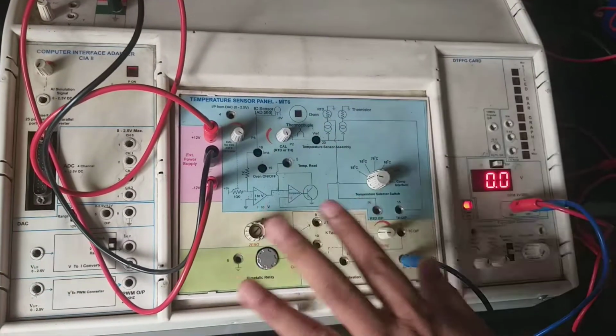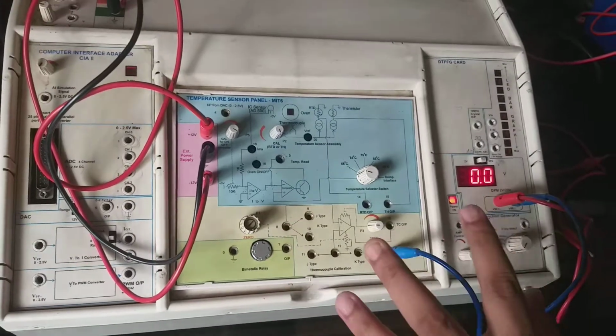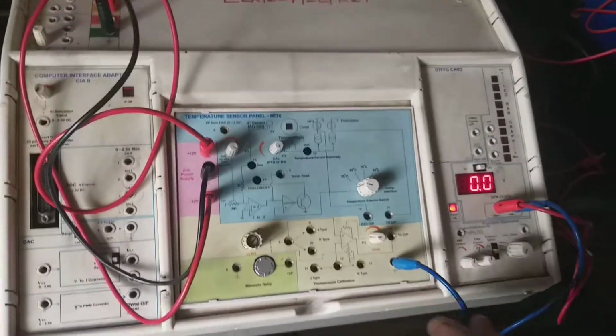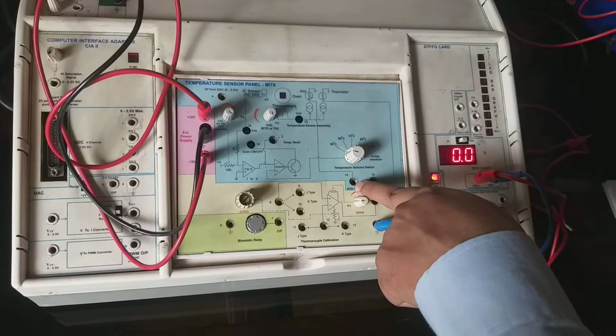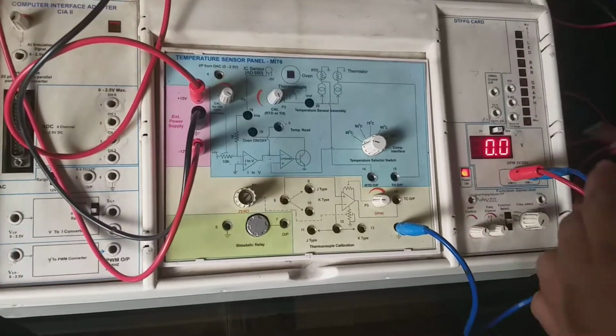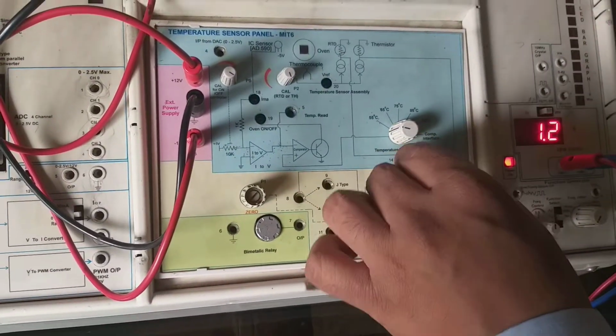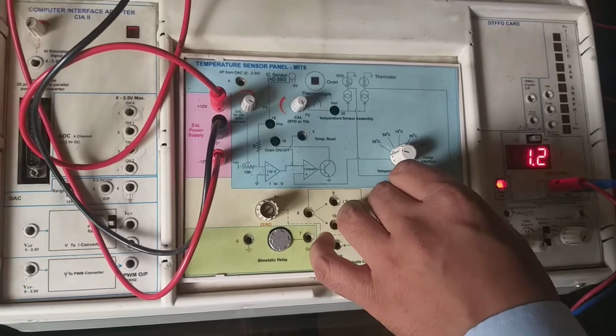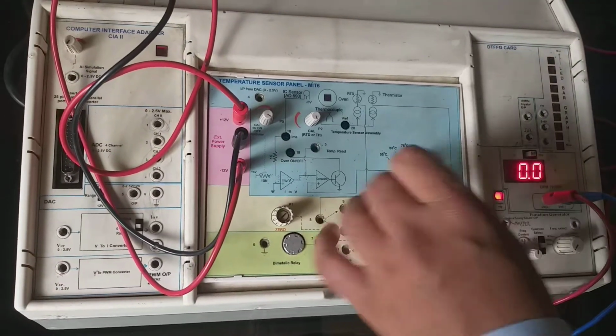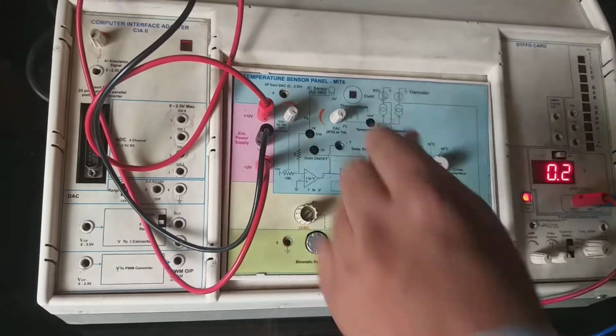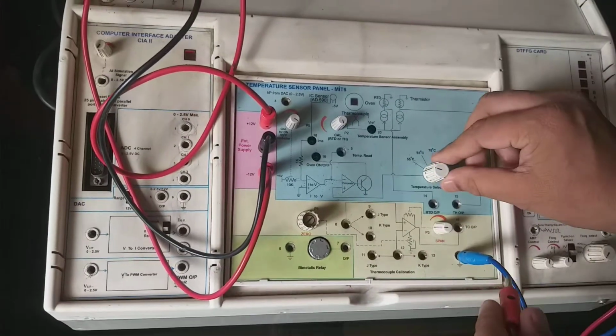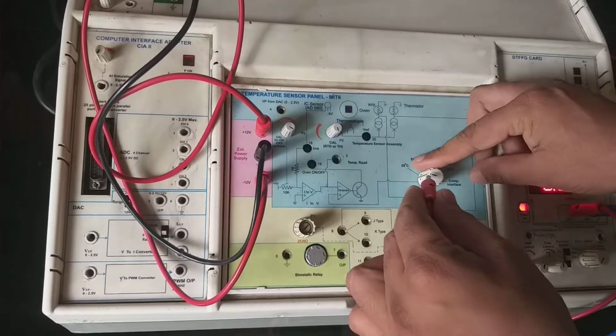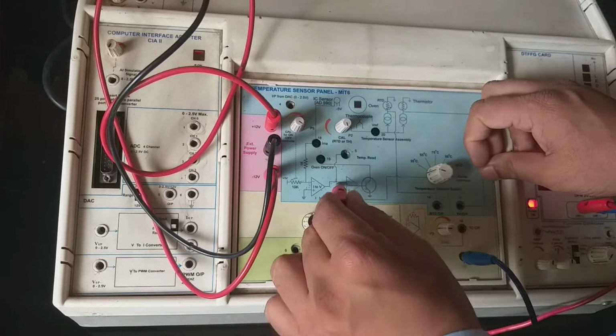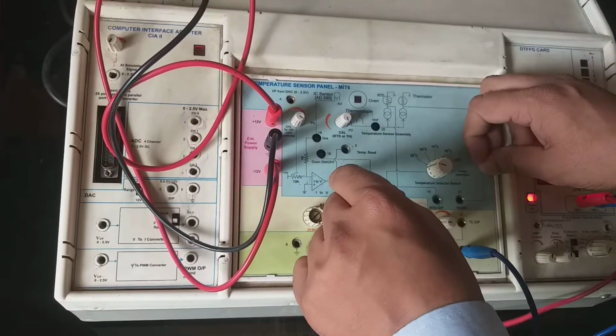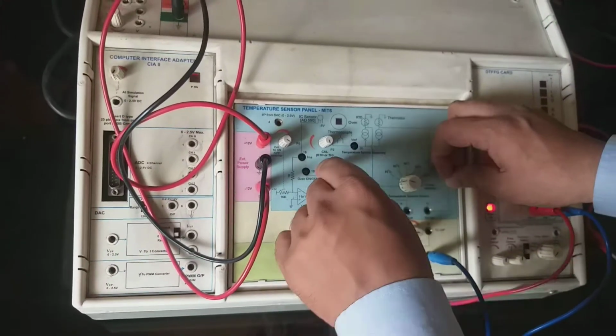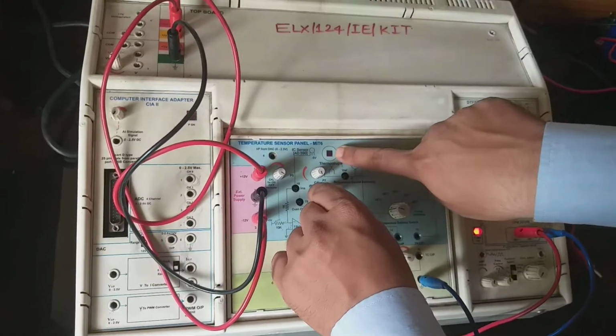So now measure the temperature in the form of voltage at the temperature read tag with a digital multimeter. This is the temperature read tag for RTD. Using this multimeter you can measure the voltage at this point, so you will observe the voltage at the temperature read tag also. At this temperature read tag I have put the reference point as 55 degrees Celsius, and this reference voltage is compared with the incoming oven voltage. When both become equal, the oven will turn off and the LED will turn off.